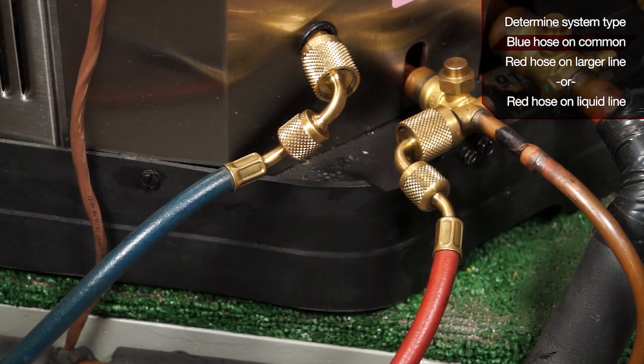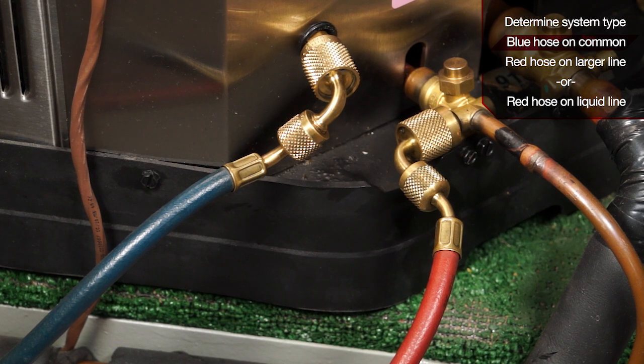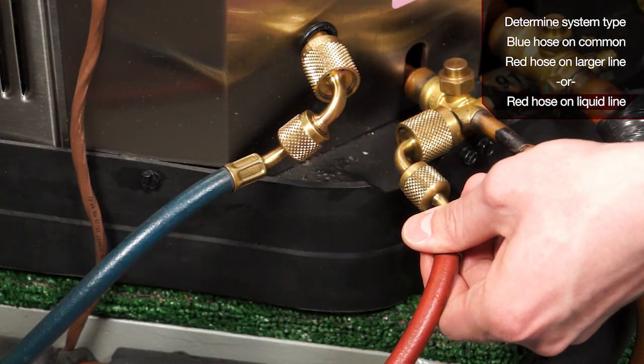When hooking up your hoses to a TXV driven system, place your blue hose on the common suction port and your red hose to your liquid line.